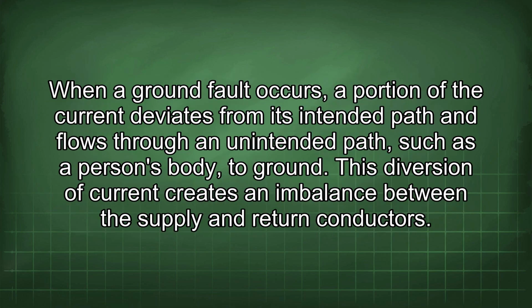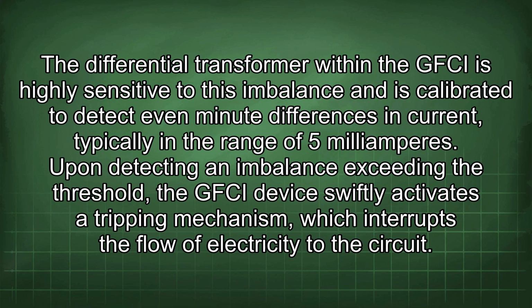When a ground fault occurs, a portion of the current deviates from its intended path and flows through an unintended path, such as a person's body, to ground. This diversion of current creates an imbalance between the supply and return conductors. The differential transformer within the GFCI is highly sensitive to this imbalance and is calibrated to detect even minute differences in current, typically in the range of 5 mA.